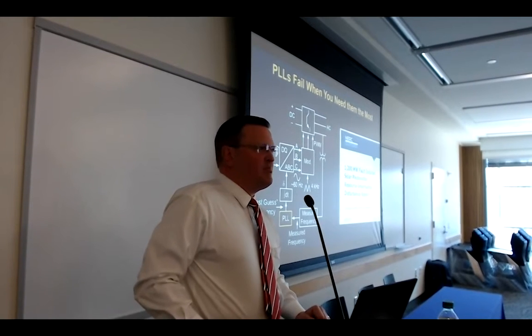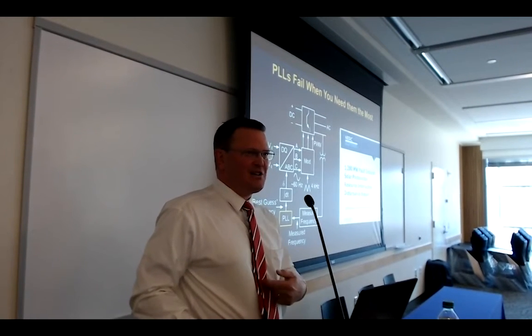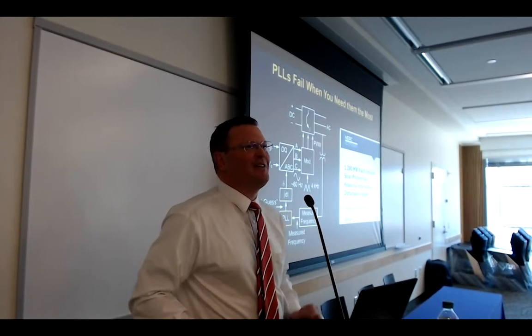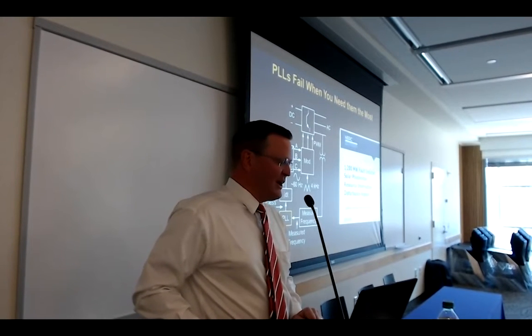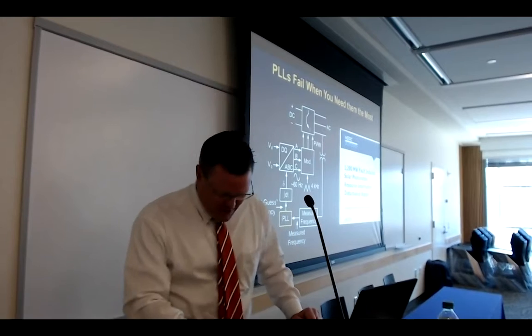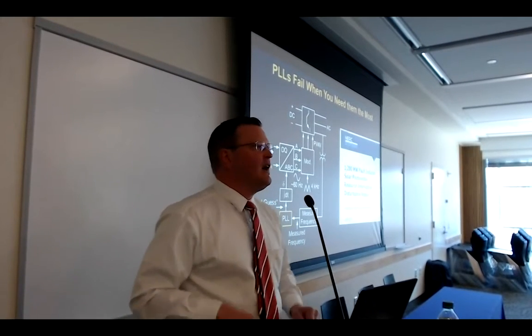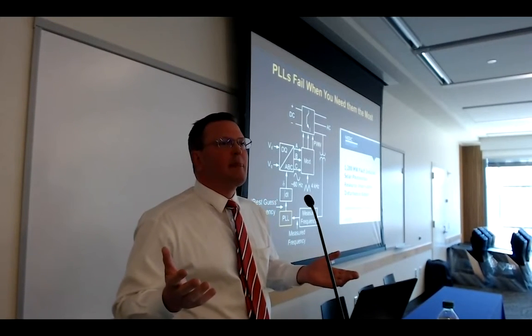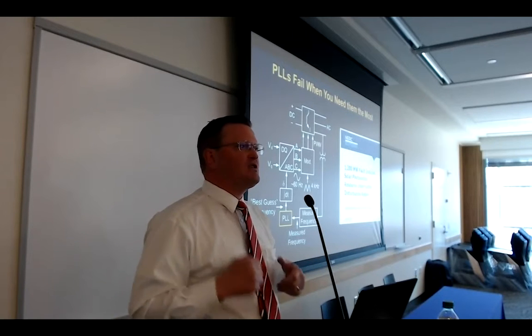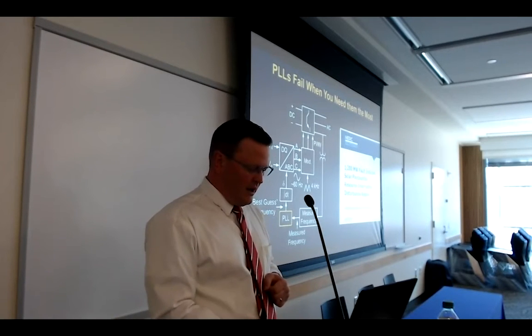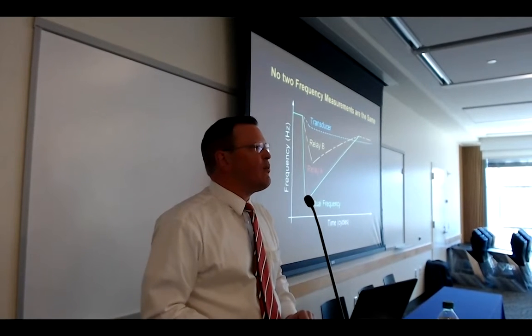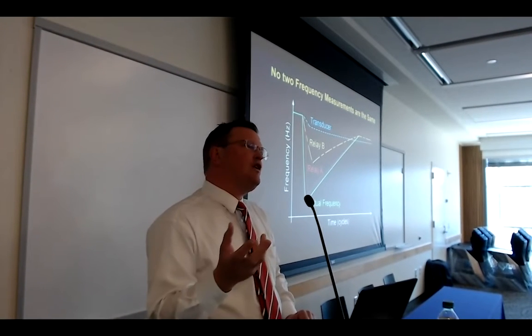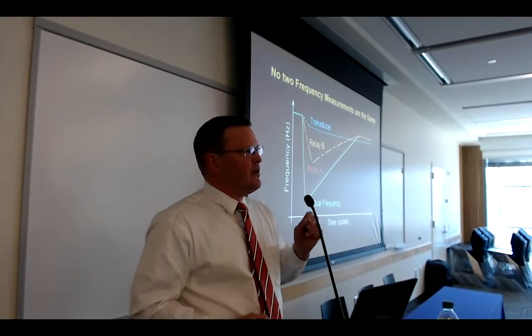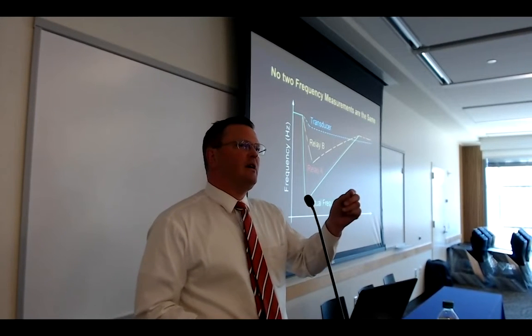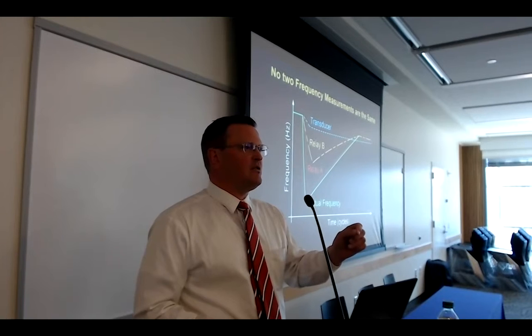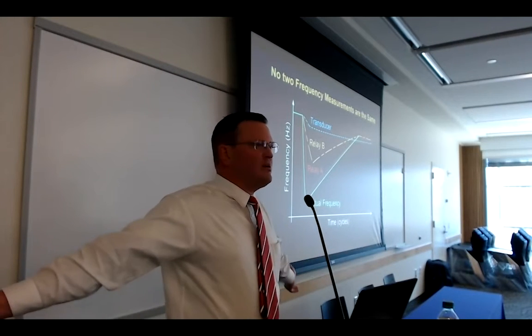I'm anti-PLL. I'll tell you right now, I need the tie with a little red circle and a line through it. I'm anti-PLL. And what this report has shown to the world is that inverters were off tripping and nobody knew about it. They were tripping because their phase lock loops were forcing units out of step. Why is that? Well, it's because phase lock loops are trying to measure something that's not always measurable, and most importantly, not easy to measure during fault conditions. When you have no voltage, how are you going to measure frequency?